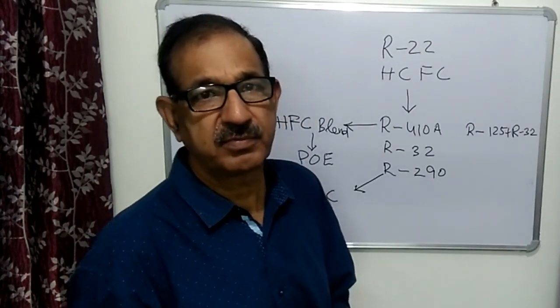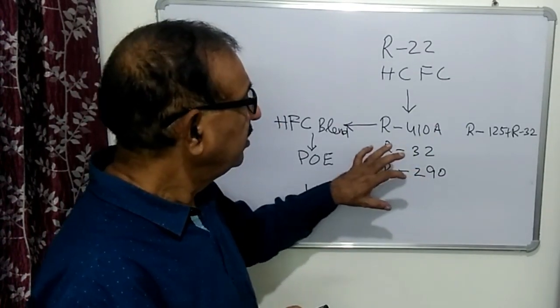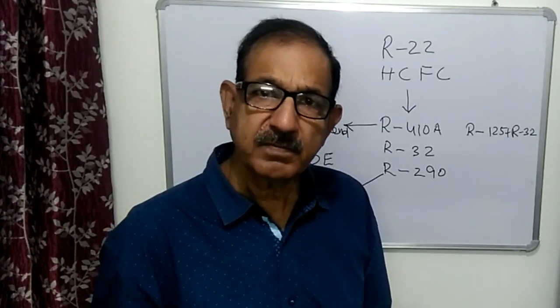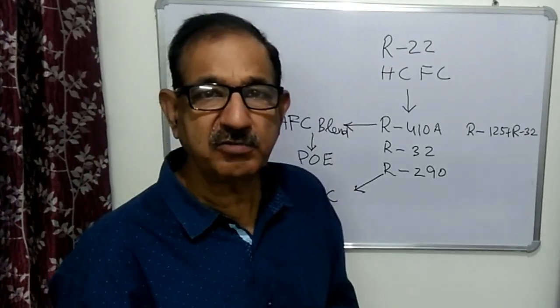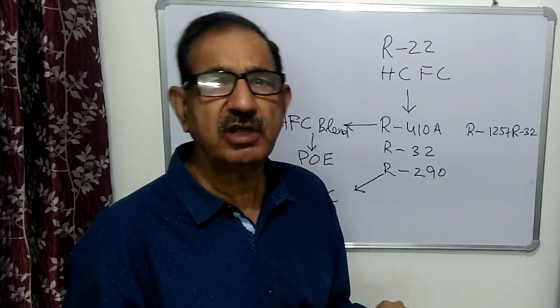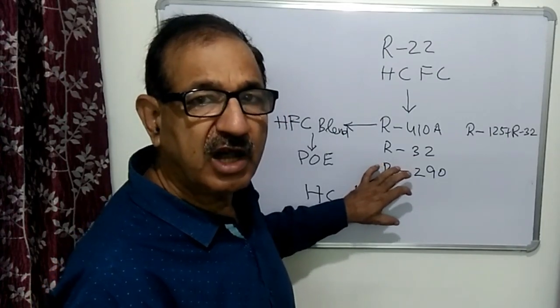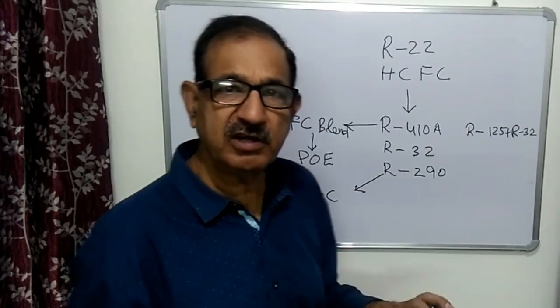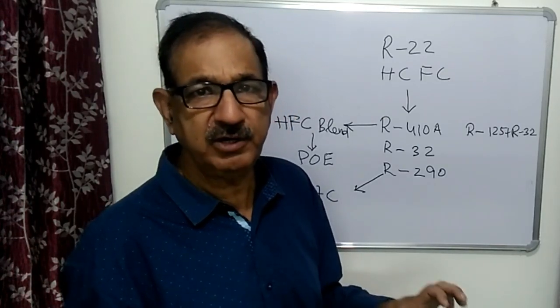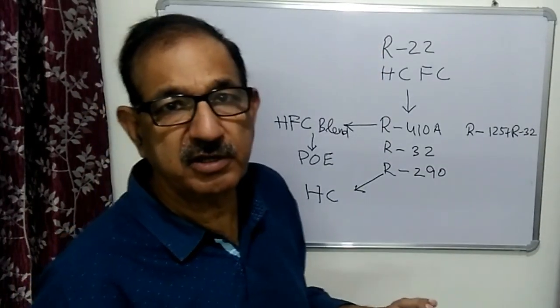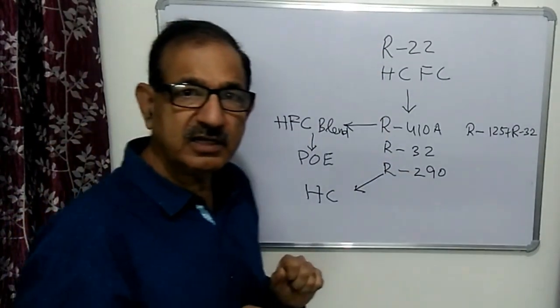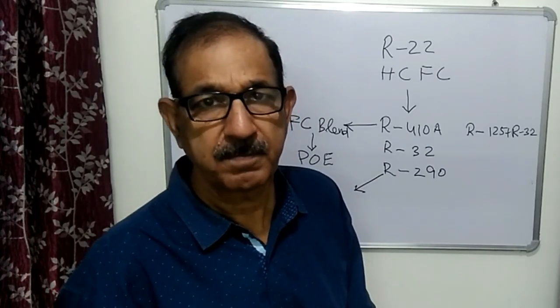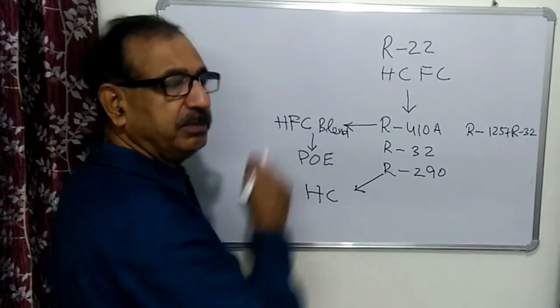The advantage of R290 is that it is very similar to R22 — the pressures are very similar — and it is also called a drop-in refrigerant for R22. We need not make any changes in the refrigeration system and can charge R290 in place of R22. However, we must take care of flammability issues, as this refrigerant is highly flammable.